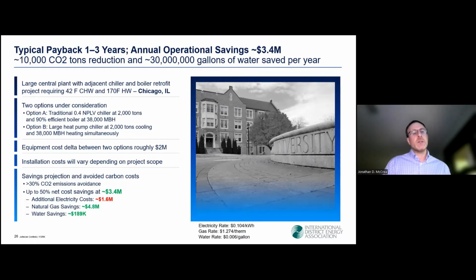of heating capacity. And just some of the other assumptions, you can see we plugged in a 0.4 average kW per ton for the existing chillers, which are going to have to do less work now once the heat pump is installed. We have a power rate we've plugged in of 10.4 cents a kWh and a natural gas rate of $1.27 per therm. And these may or may not line up exactly, of course, with what kind of power rates and gas rates that you see.